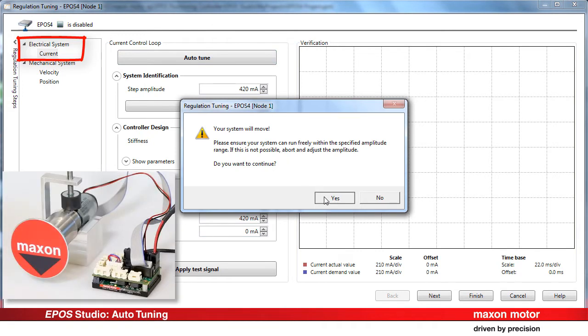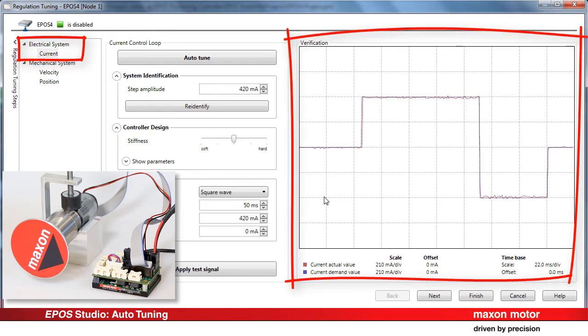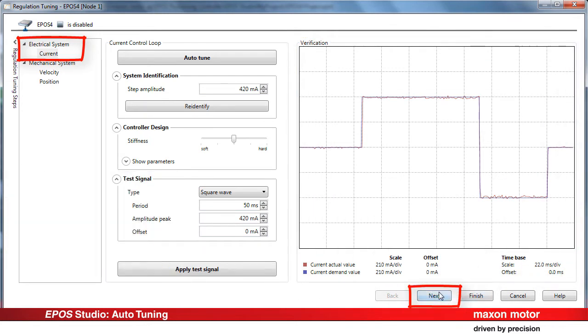Make sure that the system is free to move and continue. The tuning process first performs an identification of the electrical response and parameterizes the current control loop. Then, a test signal is applied to verify the system behavior. Check the result and the quality of the control in the verification window. Press next.